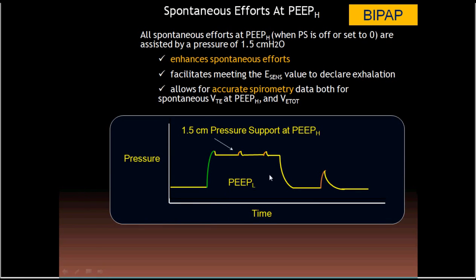Some ventilators, when there is no pressure support set at the high CPAP level, will automatically assist with 1.5 cm of pressure support at the high level.